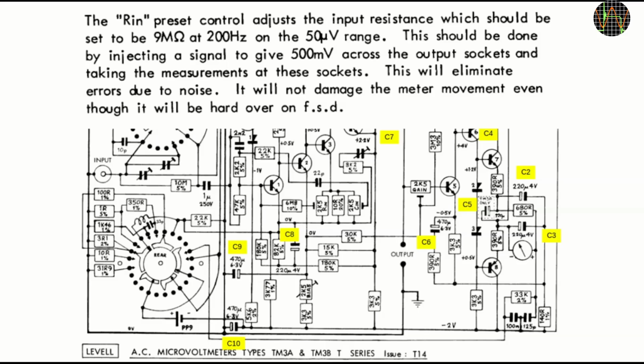The next section in the service manual has me baffled. I'm supposed to set R in, which is this trimmer here, so the meter represents an input resistance of 9 megohm at 200 Hz in the 50 microvolt range. Okay so far, but then to test this, I'm supposed to put a signal in that drives the amplifier output sockets to 500 millivolt and then take the measurements at these sockets. What measurements apart from the 500 millivolts, please? And how am I supposed to judge from that on the input resistance?